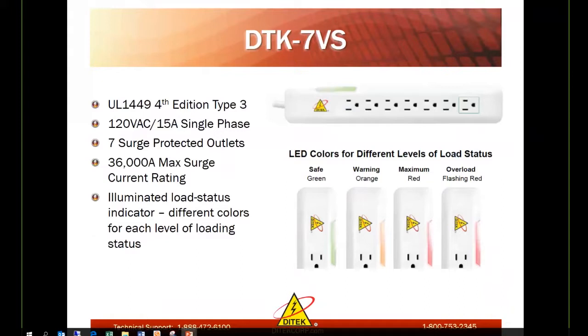Another simple plug-in here we offer is a 7VS. It's also 1449 listed, 36,000 max surge current capability. This has a load status for current draw on there. As you can see, the different colors. The green is safe, orange is a warning light, a red gives you the maximum level of current, and then the red light will start flashing if it is overloaded.